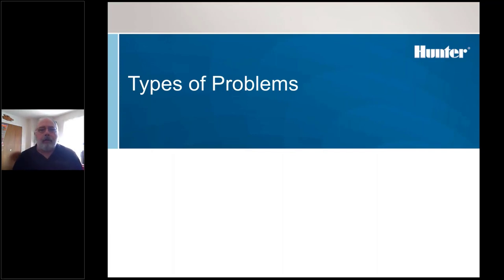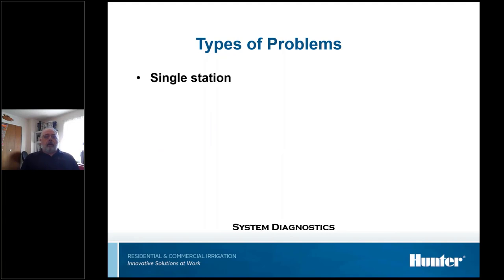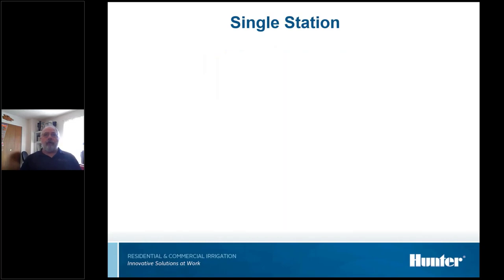So I told you, I try to simplify things as well as I can, and I break problems down on two-wire systems to three things. Either a single station, in other words, you've got individual stations that don't work, or multiple stations, groups of stations that don't work. Or usually when I get the phone call, all the stations don't work. Two-wire systems are notorious for this: when they get a shorted out decoder or surge arrestor, the controller sees that high current draw, knows it could damage the controller, and turns itself off. It'll call it a line fault. It's got various overcurrent alarms, but that's what happens.